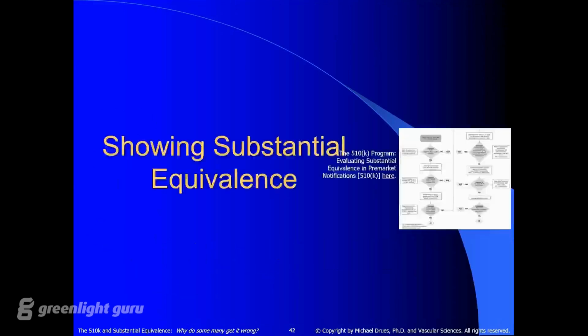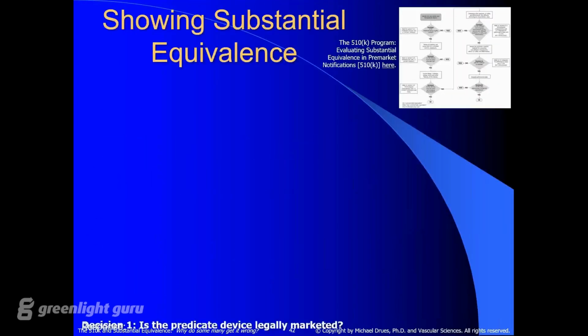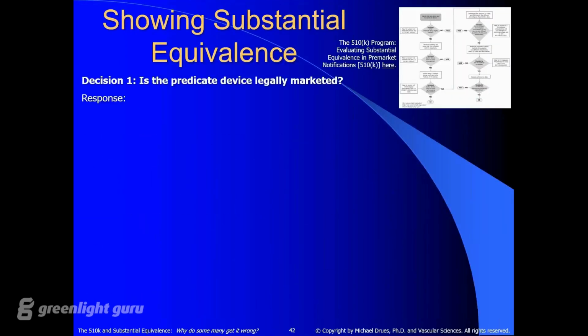So many of my friends at FDA, their advice to companies is just follow the flow chart. But that's not enough. You have to understand what this means. So digging into this some more, the different decisions in the flow chart are: is the predicate a legally marketed device? We respond to that question. That's a pretty easy one. The second decision: do the devices have the same intended use? So in this particular case, we're talking about a labeling comparison.